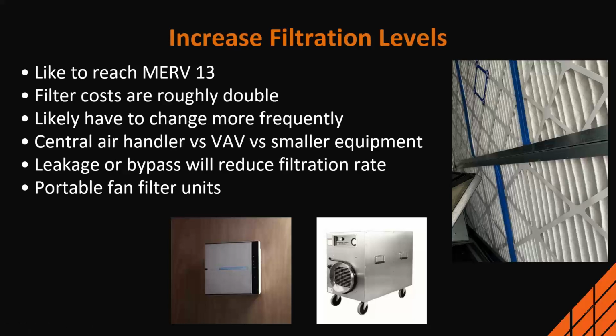We would recommend you start with your central equipment first, and the reason is, if I'm capturing roughly half the particles with 4,000 CFM on this system here with these MERV 13s, I'm going to address a lot more air, a lot more cost effectively, than if I'm going with 500 CFM and capture all of them. So basically I'm going to capture 4 times the number of virus particles with my MERV 13s because I'm doing so much more air.